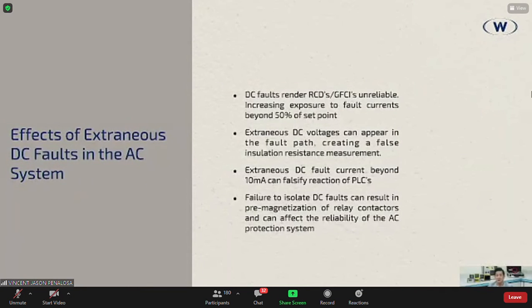So, what are the effects of extraneous DC faults in an AC system? We'll talk about AC systems for now. Those DC faults render your GFCIs and RCDs unreliable, increasing exposure to fault currents beyond 50% of the set point of your GFCI. Why? Because the typical GFCI is not DC sensitive. Also, extraneous DC voltages can appear in the fault path, creating a false insulation resistance measurement if you're already using insulation monitoring devices. Also, those DC fault currents beyond 10 milliamps can falsify reactions of PLCs. And of course, failure to isolate DC faults can result in pre-magnetization of relay contactors and affect the reliability of your AC protection system. So we need to take care of that sometimes.